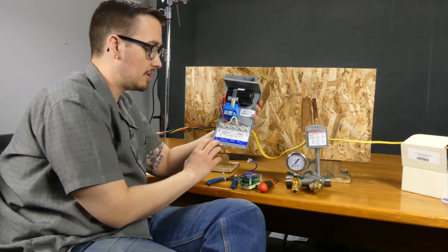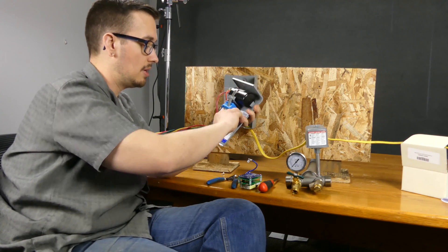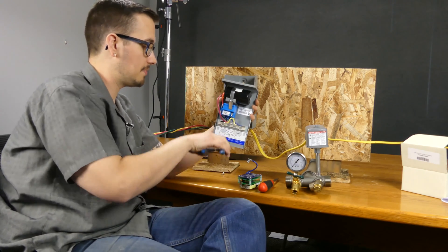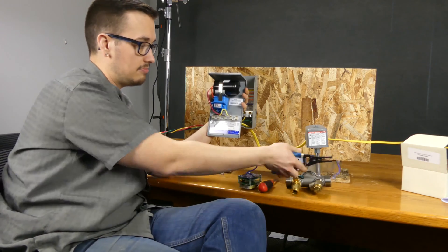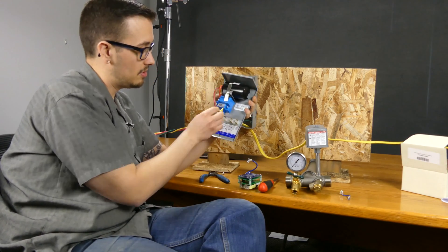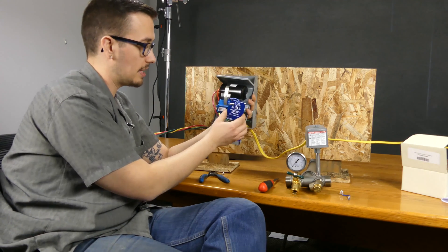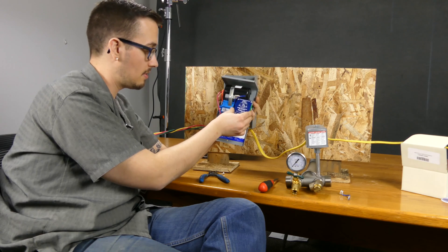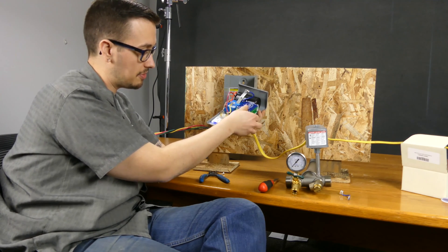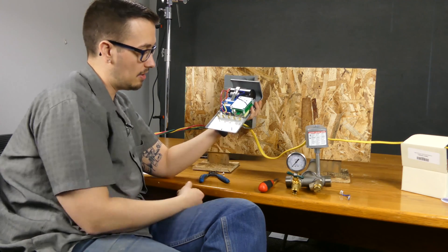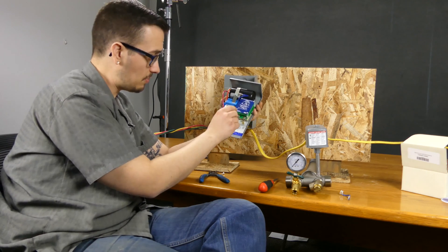So what you'll have to do is you've got this little diagram on the QD boxes - L1, L2. We're going to need to pull L1 out of there, grab the wire strippers here. So L1 we don't need that. L2 we're just going to unhook that and move it out of the way. That's where this comes in. So it's going to go in here and you've got these connectors that you want to make sure you line up so that this can be pushed down all the way. Make sure it's seated all the way to the back.